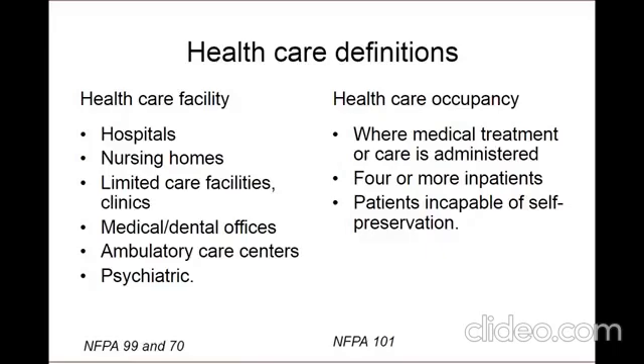So the term healthcare occupancy should not be confused with the term healthcare facility and how these codes are applicable. All healthcare occupancies are considered healthcare facilities. However, not all healthcare facilities are considered healthcare occupancies. For instance, a medical office building can be a medical facility, but under NFPA 101, it would typically be a business occupancy and not required to follow NFPA 99 or Chapter 517 of NFPA 70 for hospitals.